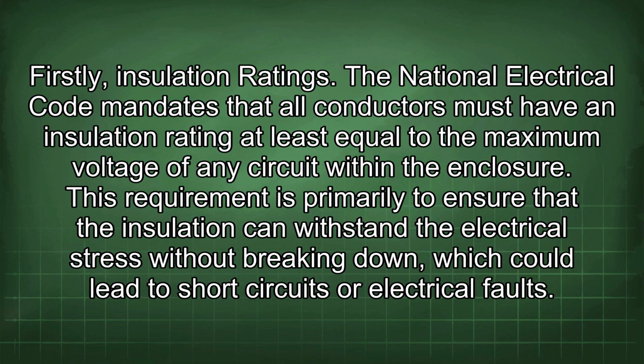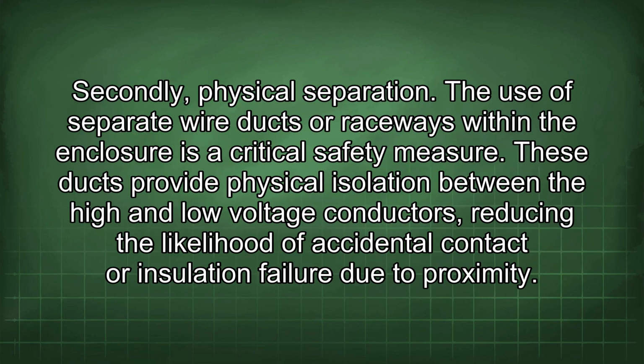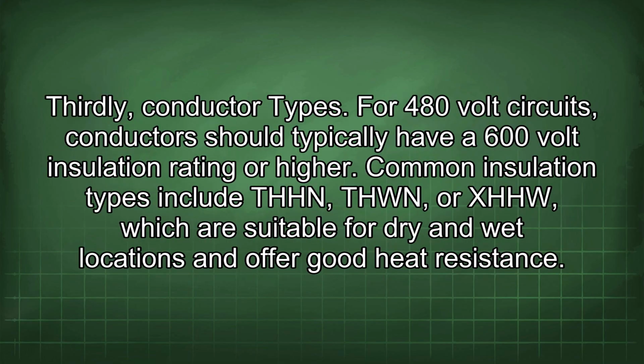Firstly, insulation ratings. The National Electrical Code mandates that all conductors must have an insulation rating at least equal to the maximum voltage of any circuit within the enclosure. This requirement is primarily to ensure that the insulation can withstand the electrical stress without breaking down, which could lead to short circuits or electrical faults. Secondly, physical separation. The use of separate wire ducts or raceways within the enclosure is a critical safety measure. These ducts provide physical isolation between the high and low voltage conductors, reducing the likelihood of accidental contact or insulation failure due to proximity.